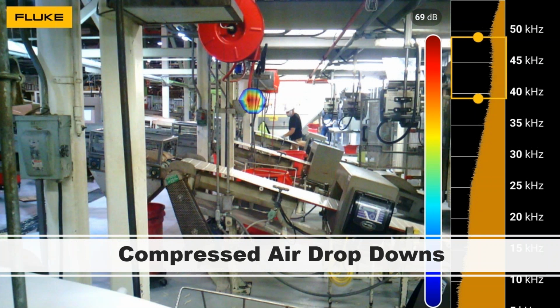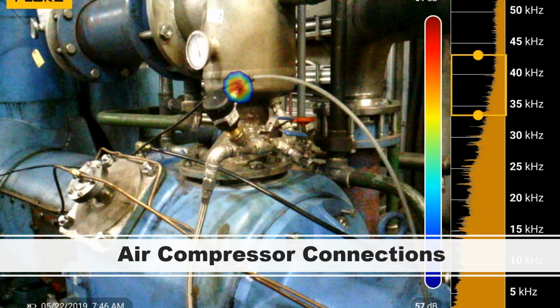Basically look at where the tools connect to the drop downs, or the drop downs connect to the equipment that's actually utilizing the compressed air. You'll be surprised at what you find. A lot of low-hanging fruit to find there. Any kind of connections you can think of, whether they're push connections, they're quick connects.